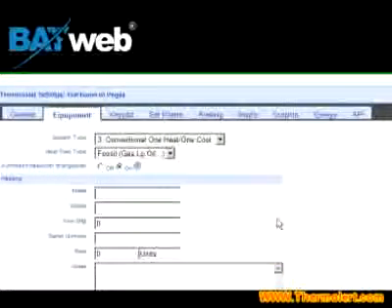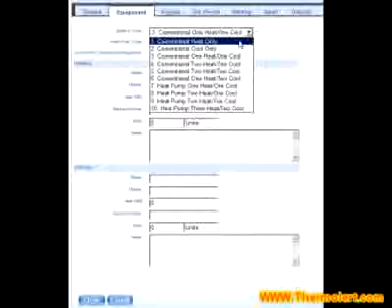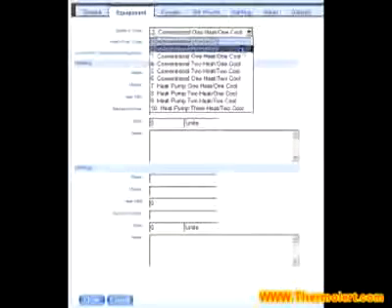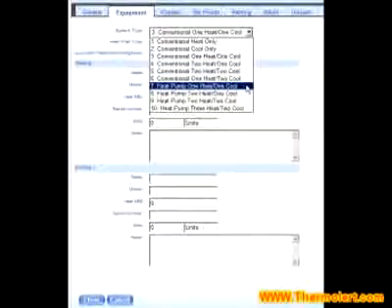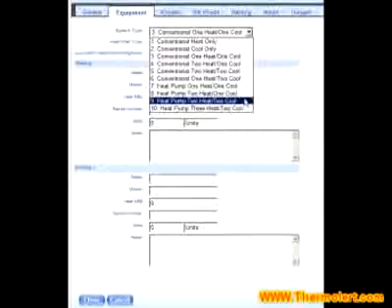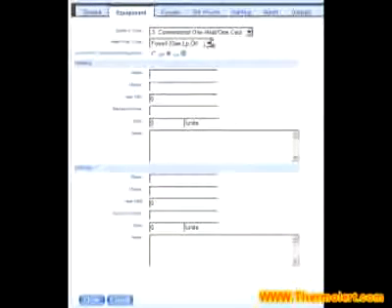The next tab is the Equipment tab, and this is a really important tab because it denotes what kind of equipment you have — do you have a heat pump, conventional heating and cooling, conventional heat only, cooling only, and so forth. It is very important to select the type of air conditioner that you have. Most of the air conditioners here in Las Vegas are heat pumps, so they have a reversing valve, and you need to make sure that the reversing valve wire is hooked up and the software is selected appropriately.